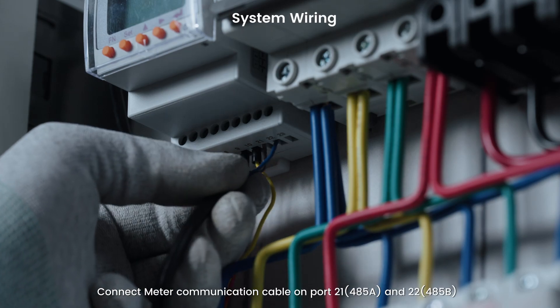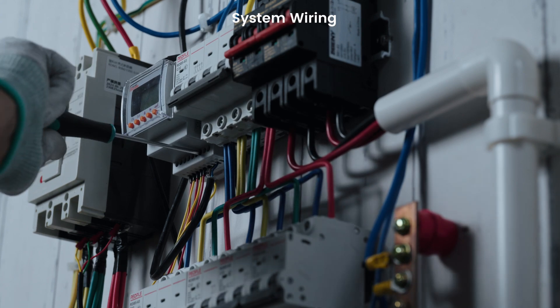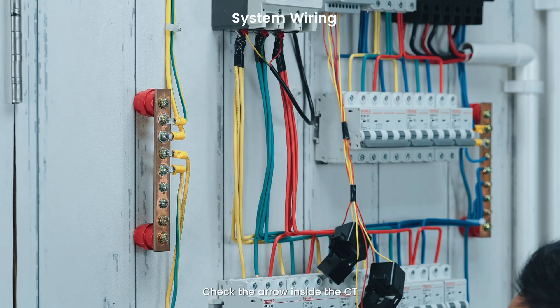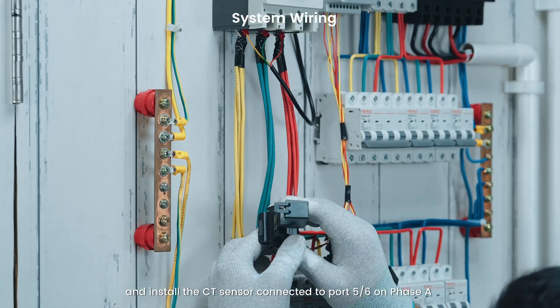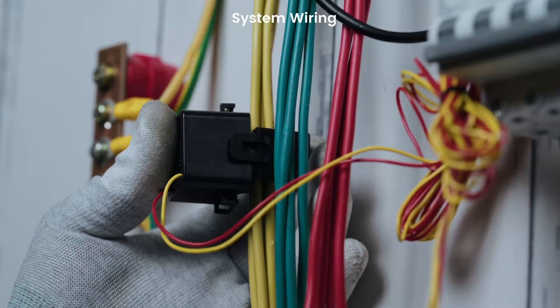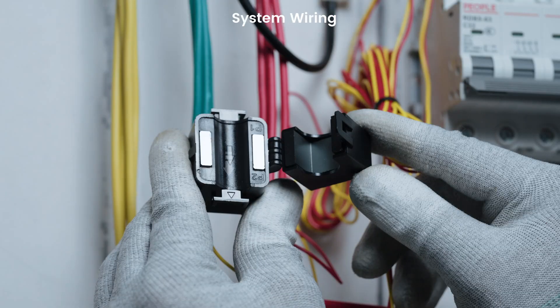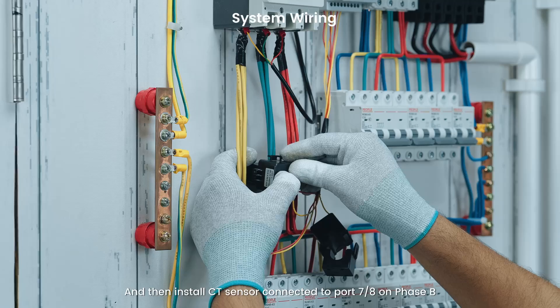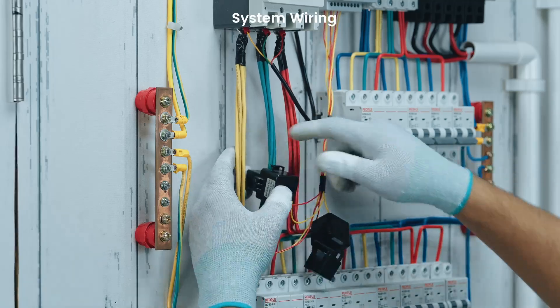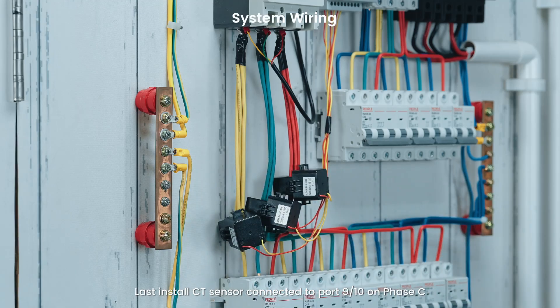Connect the meter communication cable on port 21 (485A) and port 22 (485B) and tighten them well. Check the arrow inside the CT and install the CT sensor connected to port 5–6 on phase A. The CT arrow shall point to the loads direction. Then install the CT sensor connected to port 7–8 on phase B. Finally, install the CT sensor connected to port 9–10 on phase C.